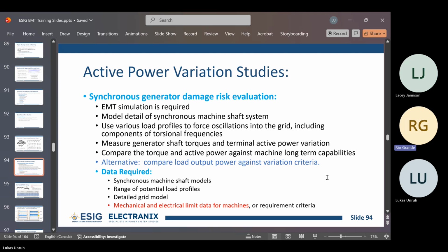And the next one here, the load profile, right? We have to make some sort of assumption on what sort of injection the load is going to be putting out onto the system. In operation, it's going to be whatever load process is running on it. And when you talk to the load vendors, they're quite hesitant. They'll never tell you that, hey, we're going to do exactly this profile with no variation. They're basically going to say it's roughly going to look something like this, and they might give you some indicators saying this dip might occur every second.